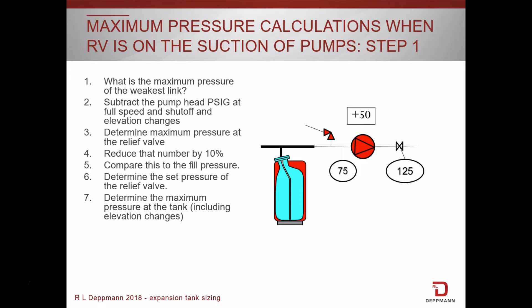Next, that relief valve will start to weep at 90% of its setting, so we want to give ourselves a 10% buffer. To do that, we need to subtract 10% from 75 psi. That gives us a maximum pressure at the relief valve of 67.5 pounds. We would then select a standard relief valve setting below 67.5 psi. It's best to stay with standard settings whenever possible, so maybe we use a 50 psi, 45 psi, or 40 psi setting. This will also be the maximum pressure at the expansion tank.